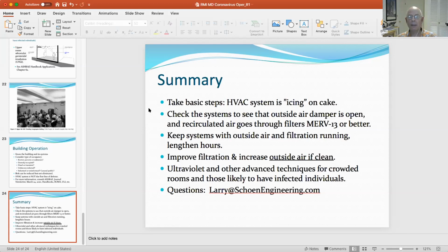I think I talked a little bit about the upgrades. There are numbers for typical lifetime of equipment. I've published some of those in the BOMA manual that I mentioned, but those are guidelines for budgeting purposes. I encourage you to look at the condition of your equipment. I've seen 10-year-old equipment, not maintained, that's in terrible condition, or that's in terrible condition because it's in a corrosive environment. I've seen 50 and even 75-year-old equipment that's been in good environments and treated well, and we keep it running.